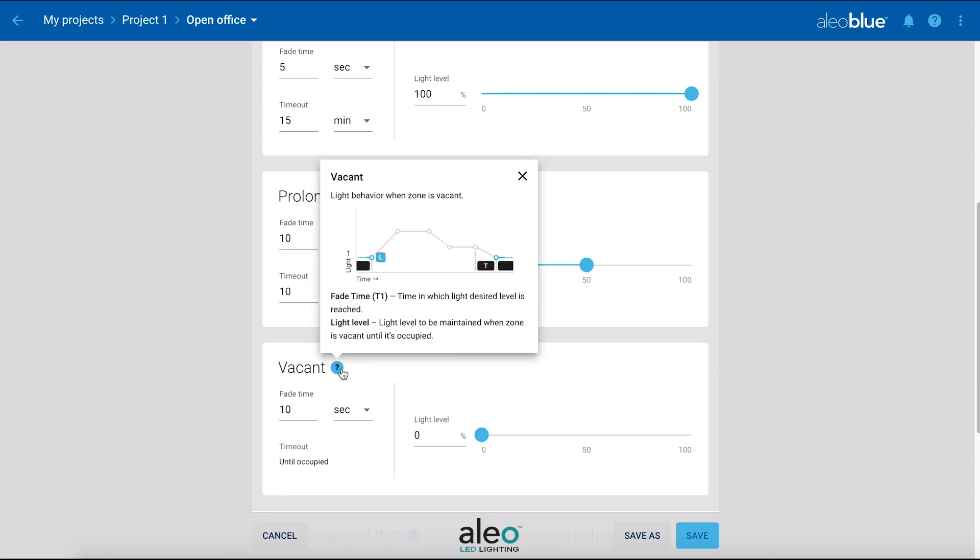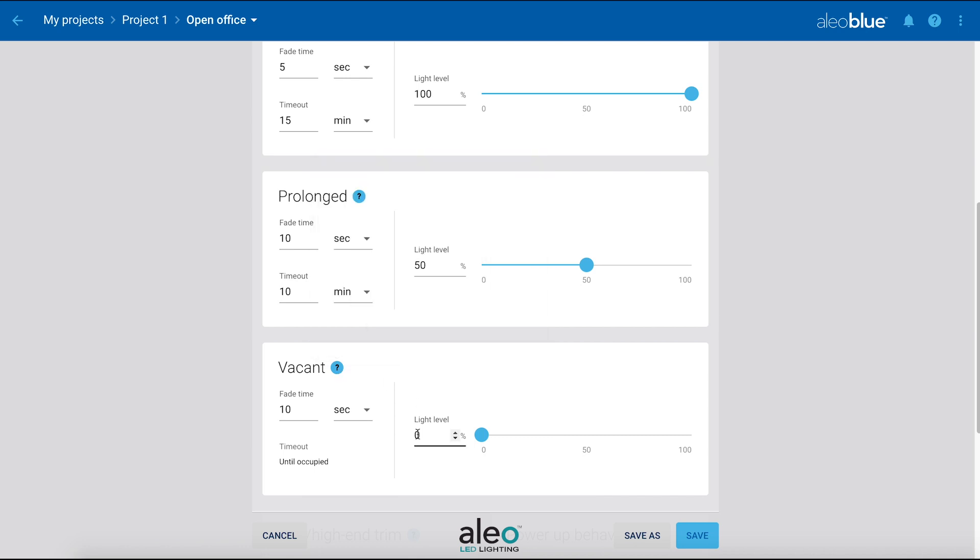Vacant is the light behavior when the zone is vacant. We will be setting the light level to 0% after 5 minutes. Once no motion is detected for that time, the lights will turn off.